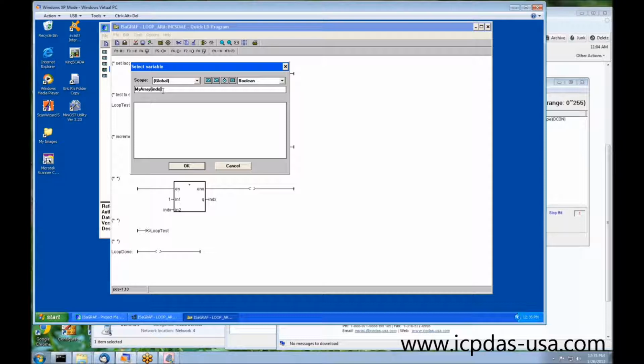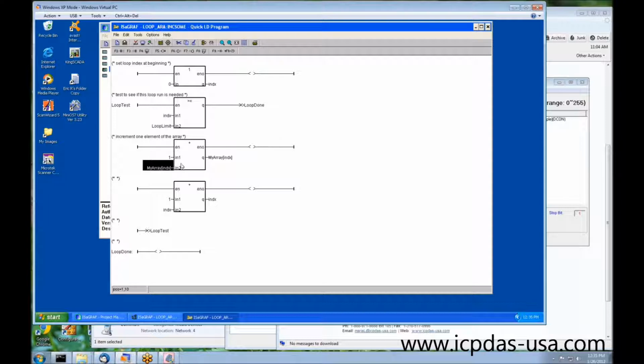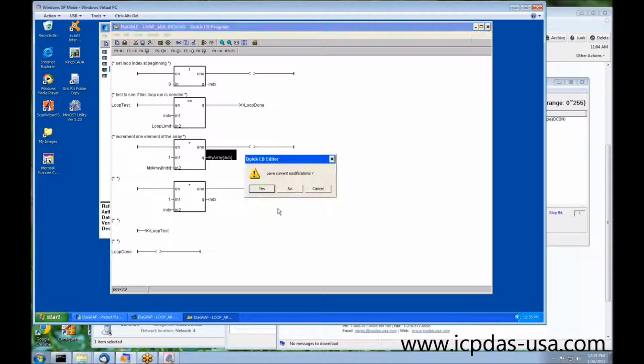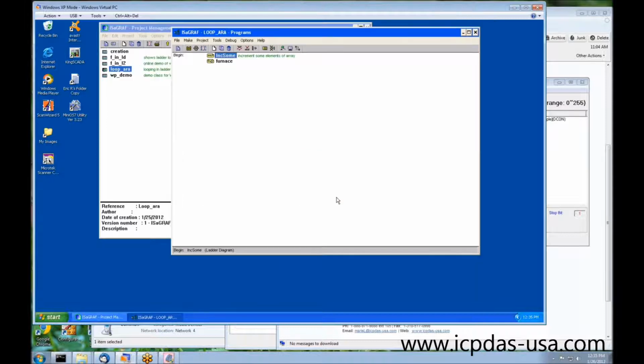And we have to keep this, at least in this 3.46 version of ISaGRAF, down to 16 characters. The usual 3.55 that people are running allows somewhat longer expressions. So I had to make sure that both these names were relatively short ones. I'm not going to make any changes.